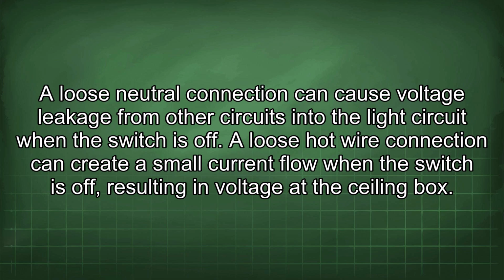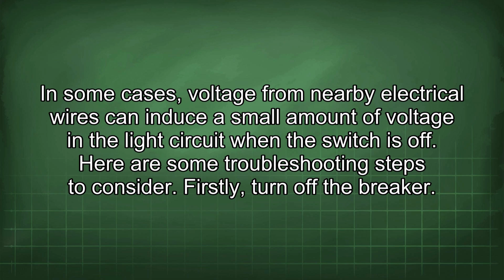A loose hot wire connection can create a small current flow when the switch is off, resulting in voltage at the ceiling box. In some cases, voltage from nearby electrical wires can induce a small amount of voltage in the light circuit when the switch is off. Here are some troubleshooting steps to consider.